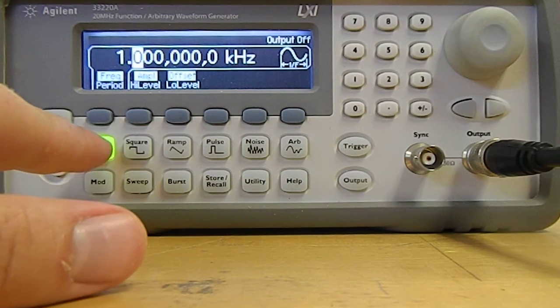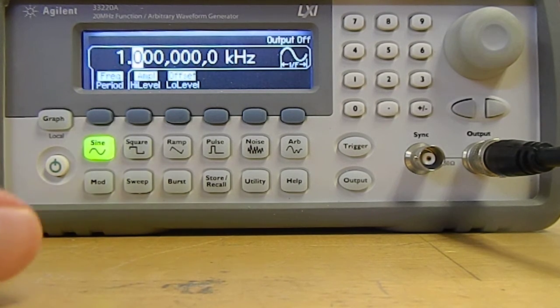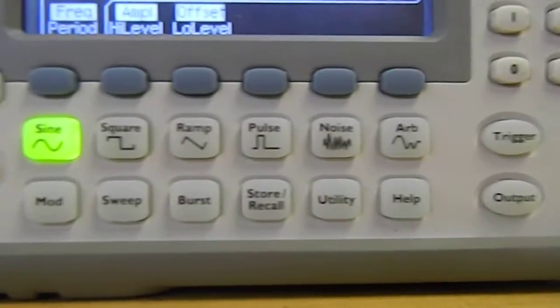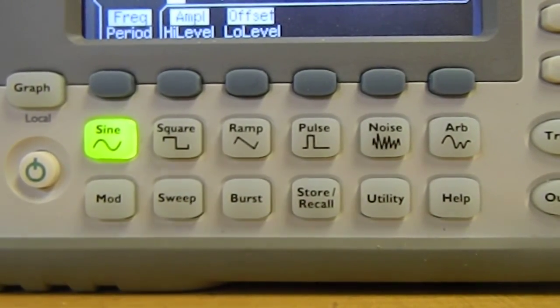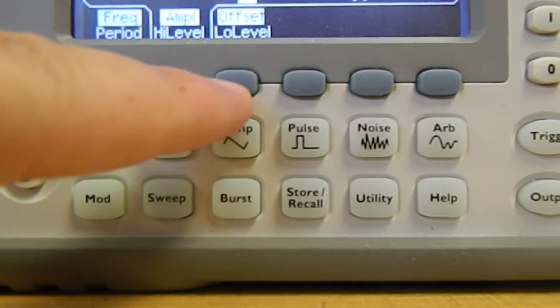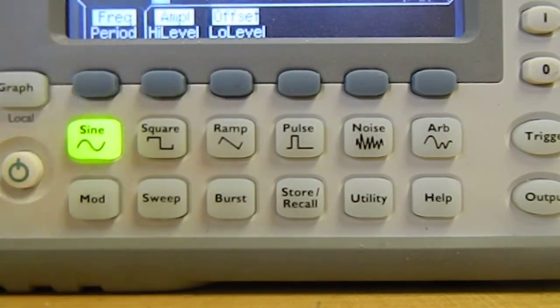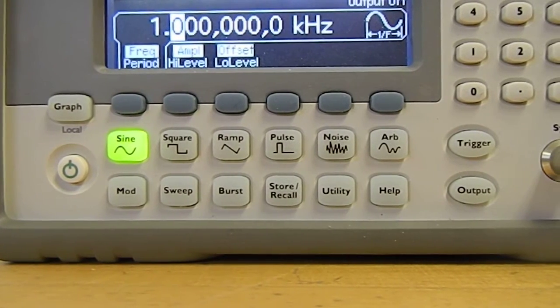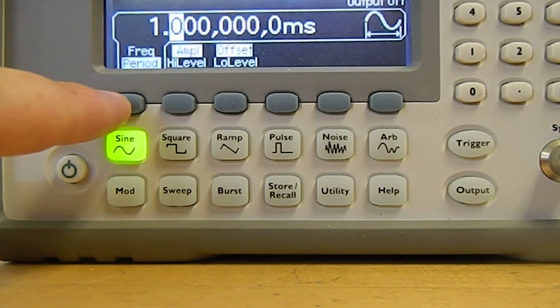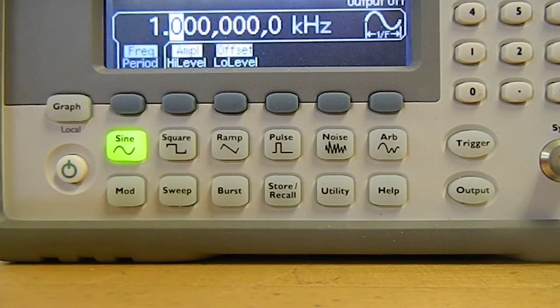Alright, so let's start with a sine wave, and then if we want to change characteristics of the sine wave, what we would do is use these blue soft keys corresponding to things going on on the screen. So you can see that there's frequency, amplitude, and offset. For frequency, you simply click on frequency. If you click it again, it allows you to set the period rather than the frequency, but we'll stick with frequency.